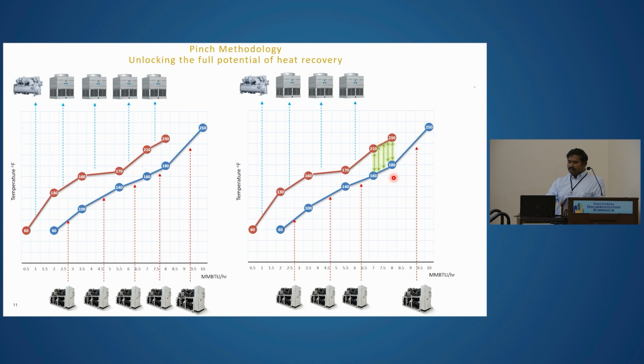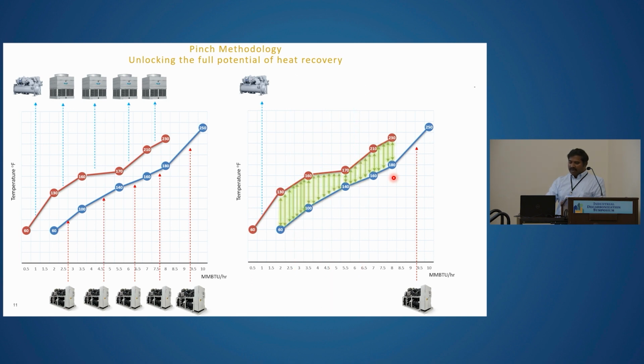So likewise, above the pinch point and below the pinch point, do direct heat recovery. And then what is left over is the remaining low-grade waste heat, where direct heat recovery is not possible, and they need high-grade useful heat in their particular process.